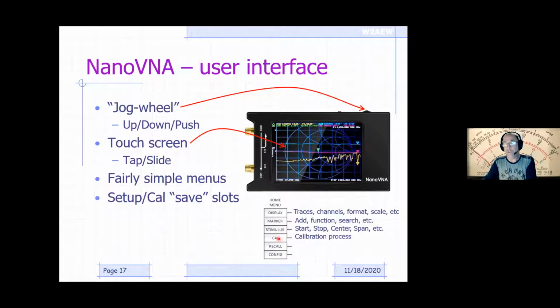When you do calibrations, like I mentioned earlier, the user calibrations, there are memory slots where you can store that calibration so that you can recall it later. So if there are measurements that you make reasonably often, maybe you're working on a design of a filter or an antenna, and you always have a particular frequency range you want to measure over, you can run the calibration over that frequency range and save it into a slot. Anytime you want to repeat that measurement, you just recall that memory location and it's all set up and ready to go. You don't have to repeat the calibration.